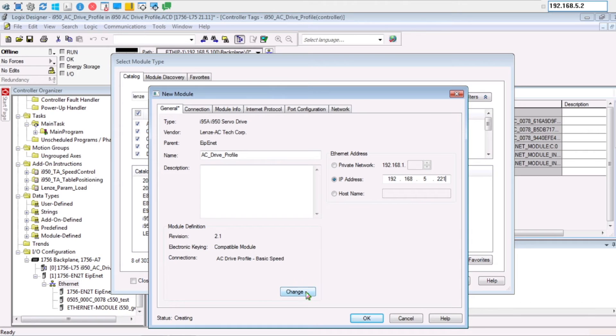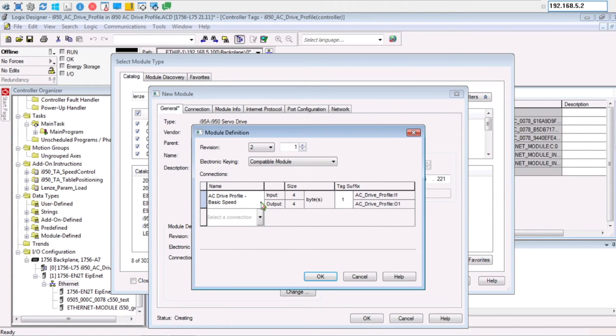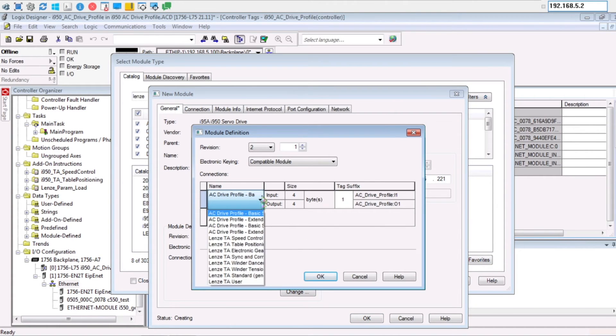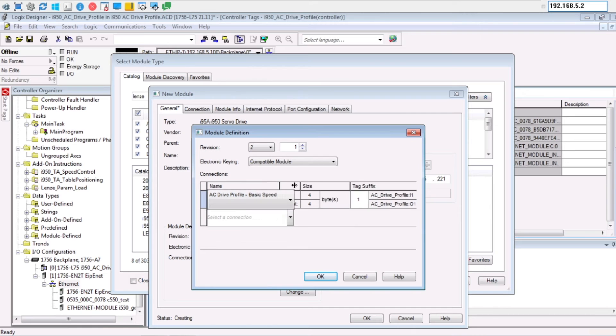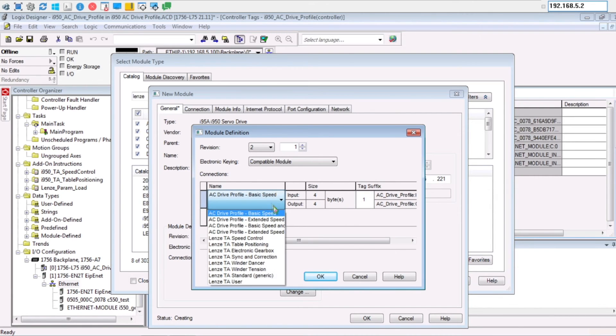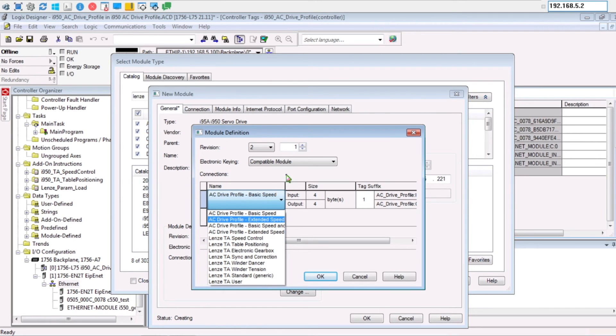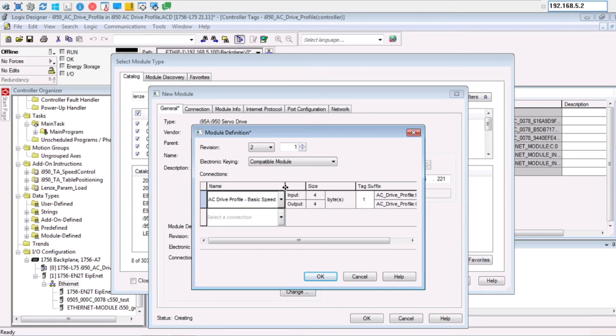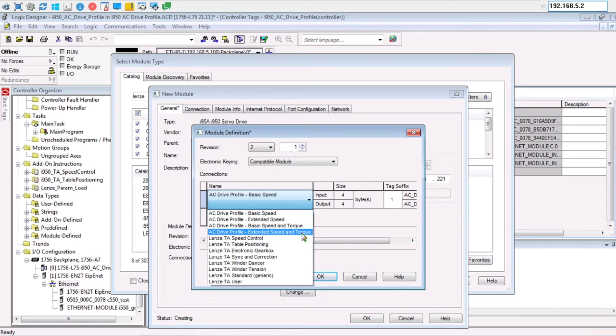Then click the Change button to select the type of input and output structure. Since I selected speed mode in Easy Starter, I can select the basic speed mode or any other AC drive profile that includes a speed mode. If you were to select torque mode in Easy Starter, then there are only two options that have the torque mode. You can see that changing between these modes changes the size of the input and output automatically.